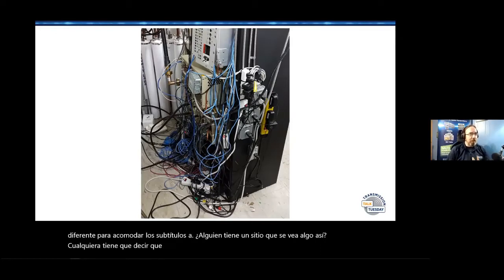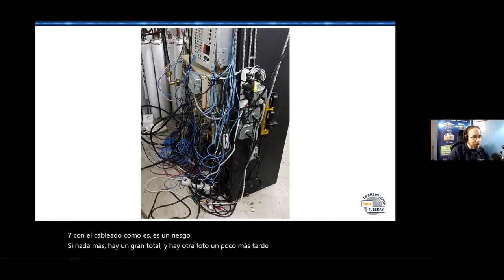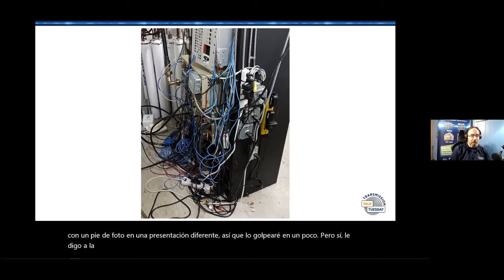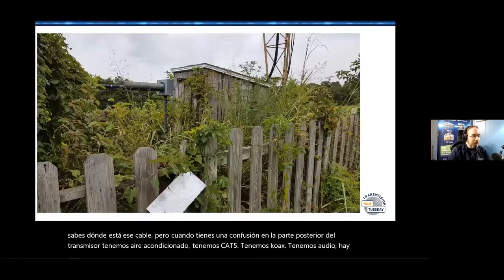In their defense, on this particular site, for the 240, there's one outlet per wire coming in, so it's not like they've strung extension cords together. But there's a lot of current being drawn in one small location, and with the wiring the way it is, it's a risk. There's another picture later that I posted with a caption in a different presentation, so we'll hit that in a bit. I tell folks, the cleaner you can keep it, the easier it is — for instance if you do a thermal scan to figure out which wire's hot, it helps to know where that wire is. But when you've got a jumble like in the back of that transmitter, with AC, Cat5, coax, and audio all mixed together, it makes it harder.